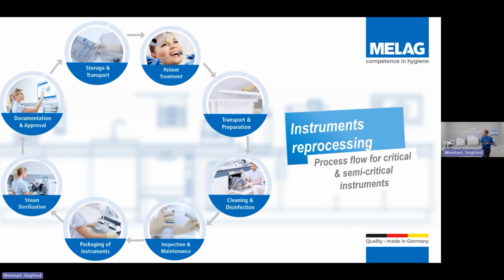However, there are certain instruments that you would want to pouch prior to going through the sterilisation. That would be something like a dental handpiece, purely because as soon as a vacuum is forced inside the chamber of a vacuum autoclave, there does run a risk that some oil could come out of those handpieces, particularly if they have been quite heavily oiled as well.